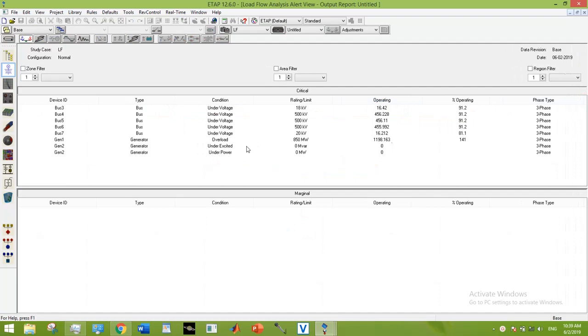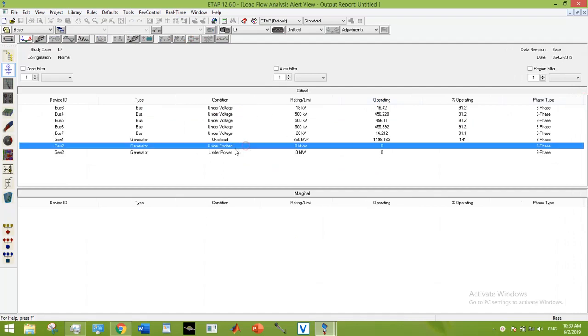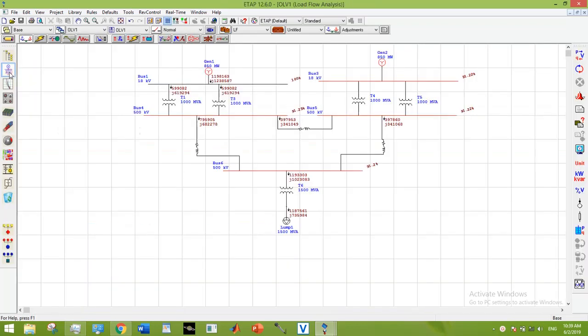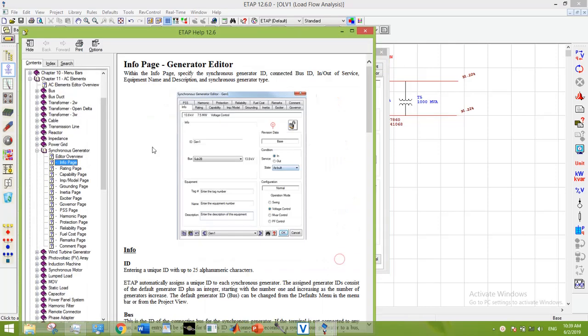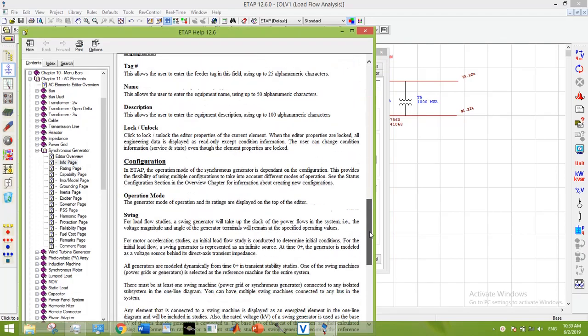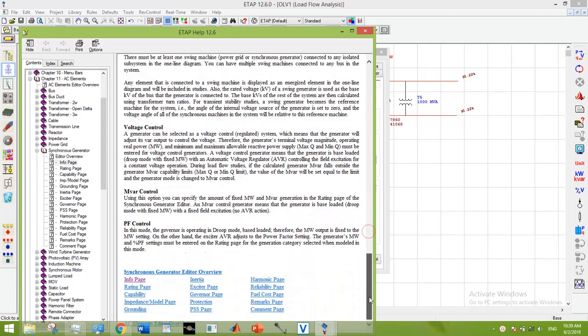First, I will be dealing with the underexcited and underpowered issue of Generator 2. Since my generator is in voltage control mode, I'm going to look for help in the menu and read what's written under voltage control.